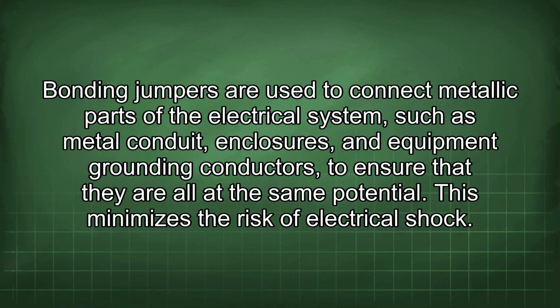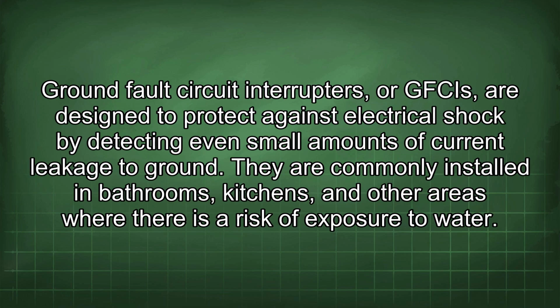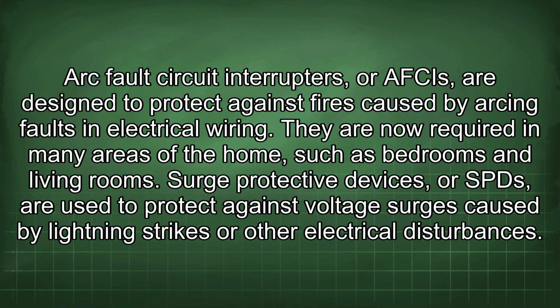Bonding jumpers are used to connect metallic parts of the electrical system, such as metal conduit, enclosures, and equipment grounding conductors, to ensure that they are all at the same potential. This minimizes the risk of electrical shock. Ground fault circuit interrupters, or GFCIs, are designed to protect against electrical shock by detecting even small amounts of current leakage to ground. They are commonly installed in bathrooms, kitchens, and other areas where there is a risk of exposure to water. Arc fault circuit interrupters, or AFCIs, are designed to protect against fires caused by arcing faults in electrical wiring. They are now required in many areas of the home, such as bedrooms and living rooms.